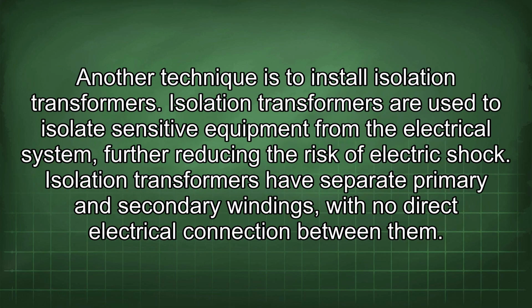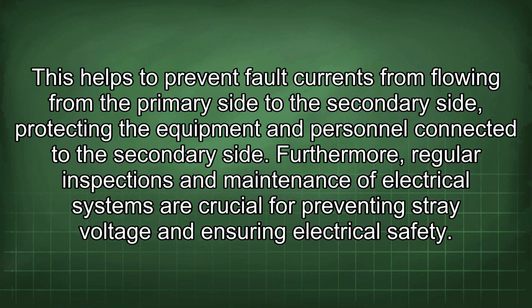Another technique is to install isolation transformers. Isolation transformers are used to isolate sensitive equipment from the electrical system, further reducing the risk of electric shock. Isolation transformers have separate primary and secondary windings, with no direct electrical connection between them. This helps to prevent fault currents from flowing from the primary side to the secondary side, protecting the equipment and personnel connected to the secondary side.